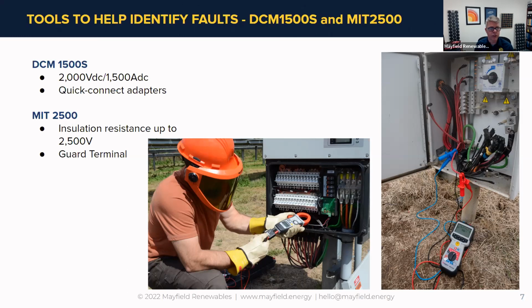Another one of the tools in the toolkit is the MIT 2500. That's Megger's insulation resistance tester. I know Mike's going to cringe a little bit, but everybody calls it doing a Megger, measuring your array, measuring your conductors, things like that. Megger is the trademark name, but insulation resistance testing is the name of the test being done. So we're checking the insulation resistance, and that's what we're showing on the right-hand side here.